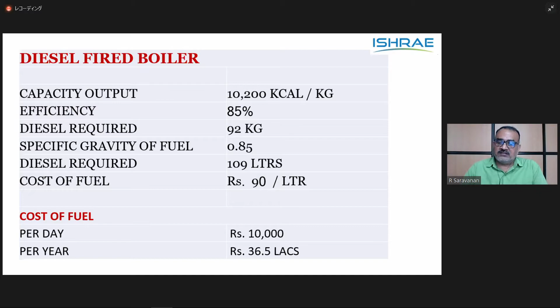When it is replaced with a heat pump, the F2RCS heat pump, which has been installed and is successfully in operation, has a COP of 3.5. The total power required is only about 266 kilowatt hours for the operation of the heat pump to deliver about 930 kilowatt of heat. So the cost of power is 2,660 Indian rupees per day, and per year it is about 10 lakhs. The total saving per year is about 26.8 lakh Indian rupees, so the payback period of the heat pump installation is less than 1.5 years in this typical installation.